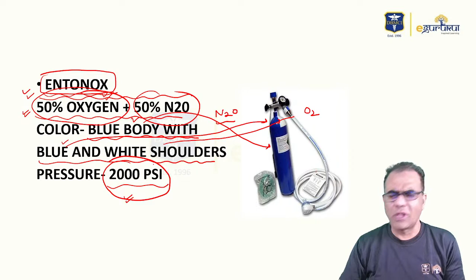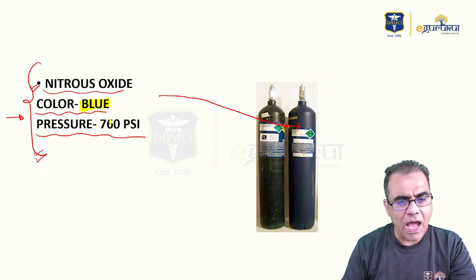The color of the oxygen cylinder is black body with white shoulders, and the pressure in a full cylinder is 2000 pounds per square inch. Nitrous oxide is stored in blue cylinders at a pressure of 760 pounds per square inch. Entonox, a combination of 50% oxygen and 50% nitrous oxide, has a blue body with blue and white shoulders, blue indicating nitrous oxide and white indicating oxygen, and the pressure is 2000 pounds per square inch, that is the pressure of oxygen.